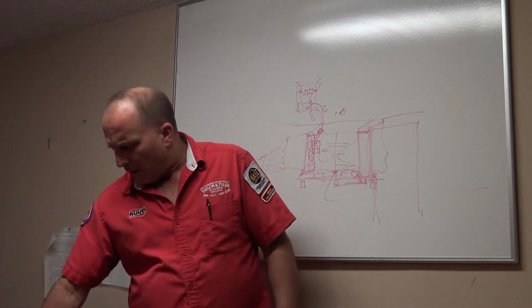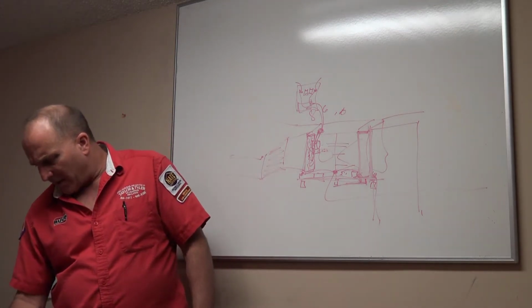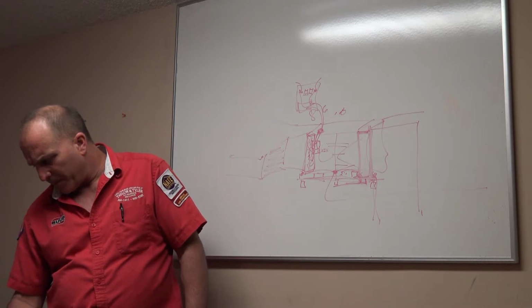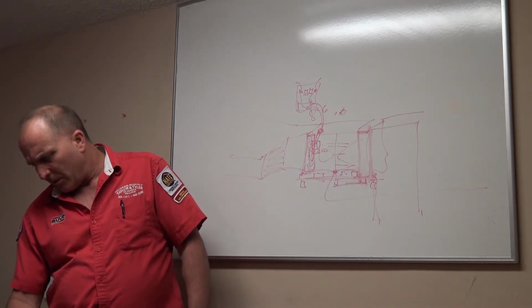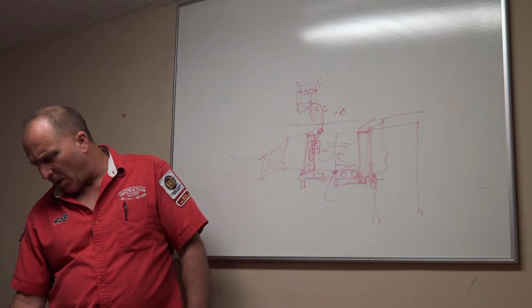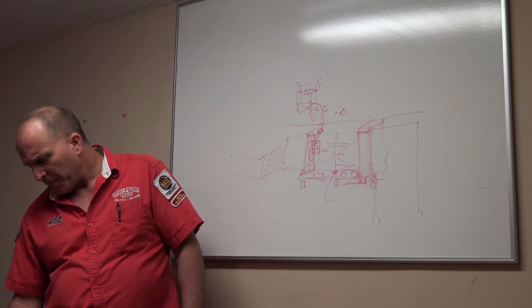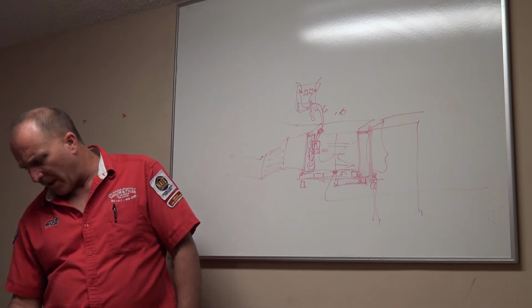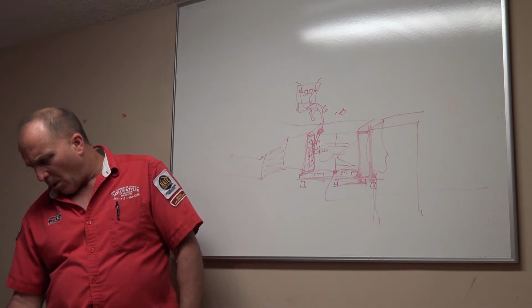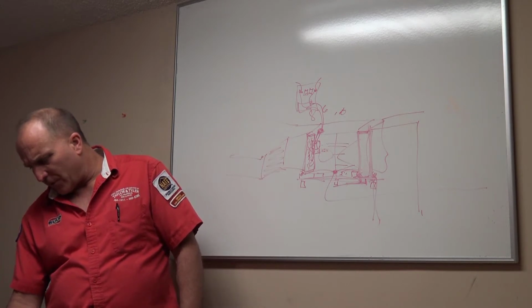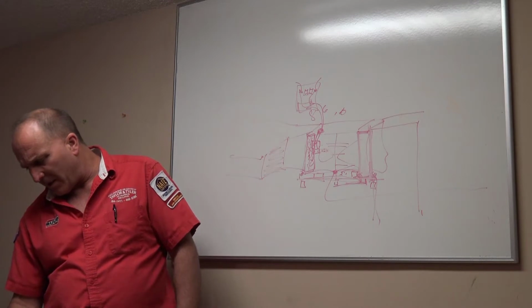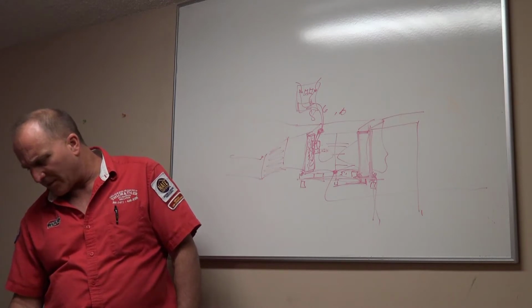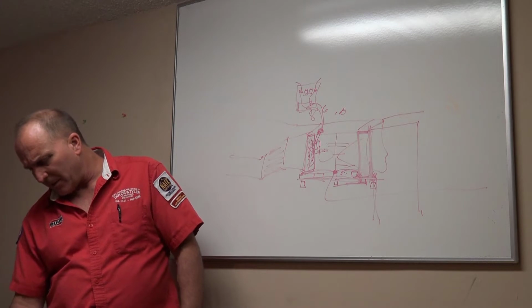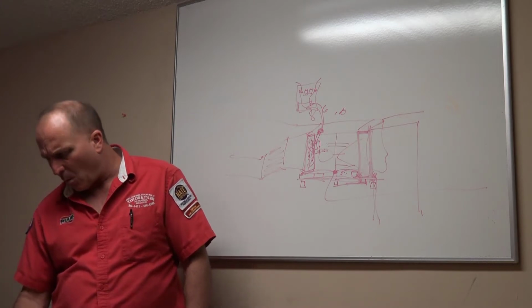That's simple. Heating elements. Check what size they are. Hint. Count the setup in the electrical compartment. Look to see how many limit switches there are. Heat sequencers. Breaker sizes. What amps does it draw? How many wires of one color are drawing amps? Add the amps or all wires drawing amperage. Verify the total amps. The correct kW heating elements in the system. Verify wire sizes for correct heating elements. If they do not match, figure out why.